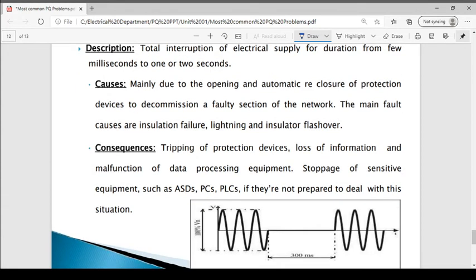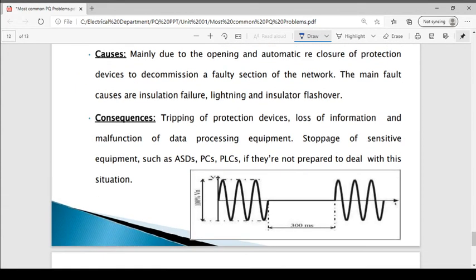It is mainly due to the opening and automatic reclosure of the protection devices to decommission a fault section of the network. That is the operation of the relay and circuit breaker. The main fault causes are insulation failure, lightning and insulator flashover. These are the causes for the very short interruption.